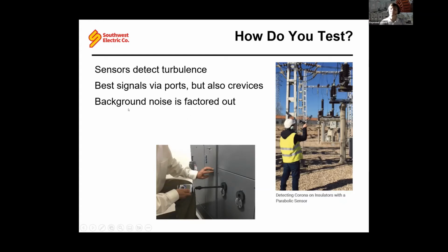Background noise doesn't apply when it comes to ultrasonic, because most of the frequencies we're looking at are well above 1,000, actually above 10,000 hertz. And most audible noise we have is well below that. Any audible noise going on around you is so far left on the spectrum that it doesn't even get recorded. This allows you to purify that signal and be able to analyze, detect, or identify what the disturbance is about. And once you find an area of concern with ultrasonic testing, you can start using your IR scan and hone in on that problem more effectively.